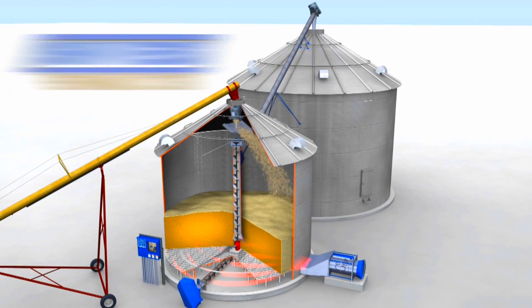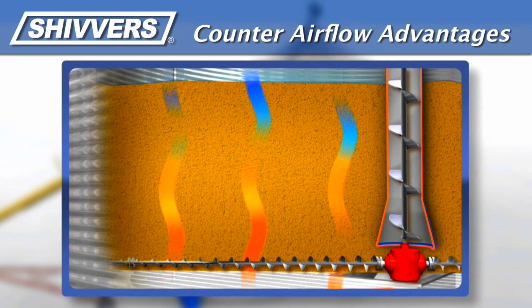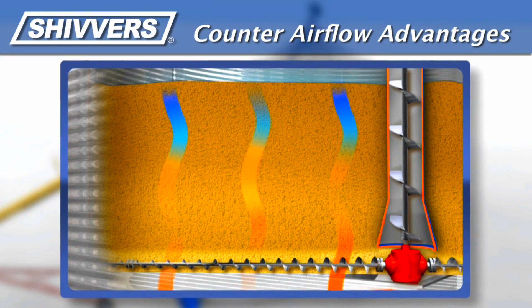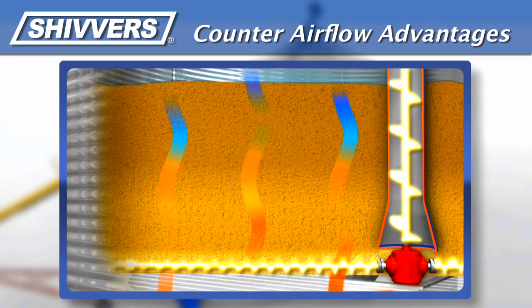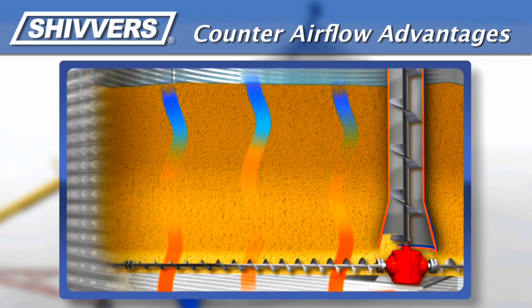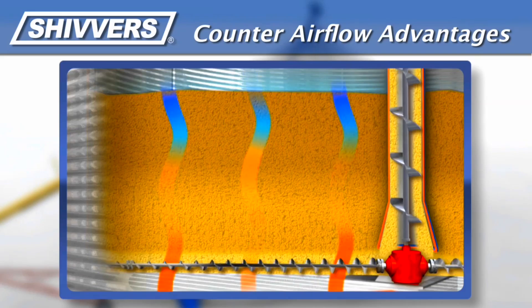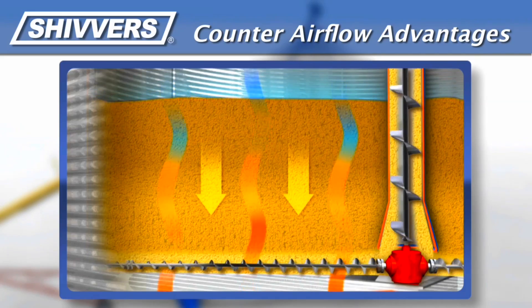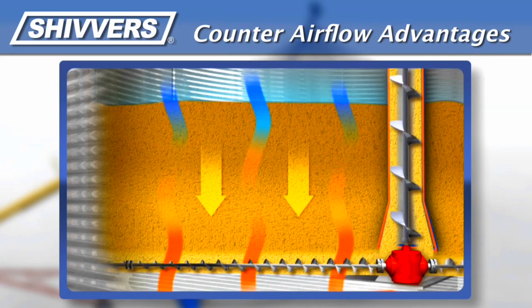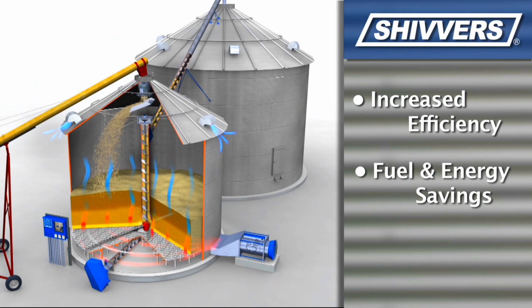The Shivvers system uses a process called counter-flow technology. With counter airflow, air moves upward through a thick bed of grain in the bin — at least three to eight feet deep — as the grain itself moves slowly downward. This counter airflow has several advantages over traditional cross-flow methods: since the heat is in contact with the grain for a longer period of time, most of the heat is used to remove moisture before it is exhausted, increasing efficiency and saving money on fuel and electricity.